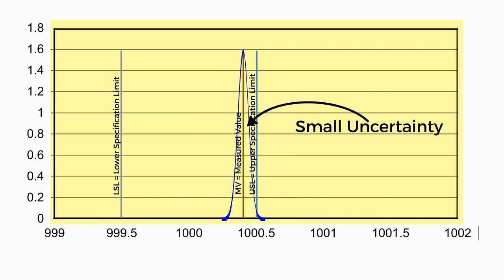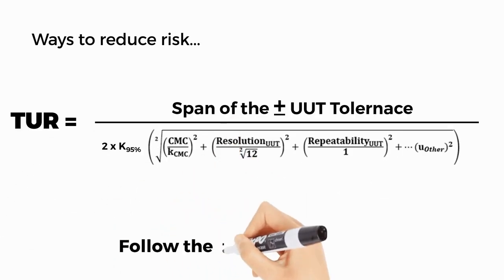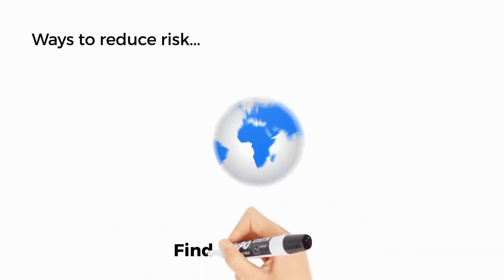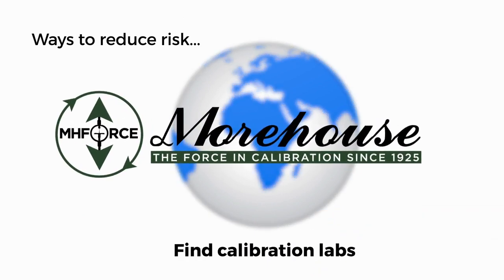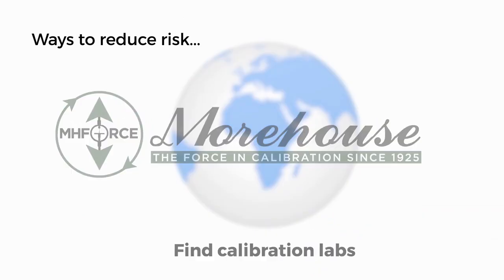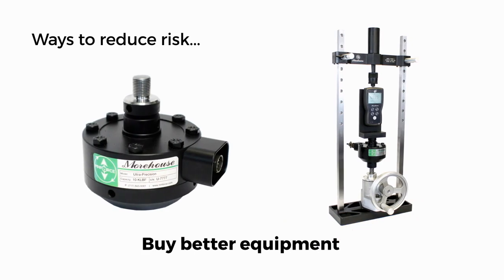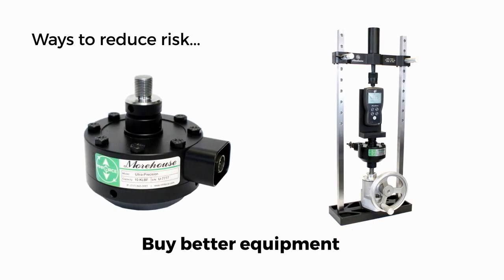Such is the case in this example when Morehouse performs the calibration. The ways to reduce the risk are simple. Follow the formula for TUR. Find calibration labs, such as Morehouse, with the lowest measurement uncertainties. Buy better equipment that is repeatable and has enough resolution.